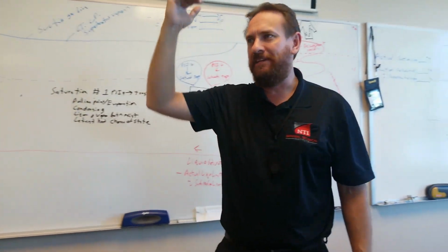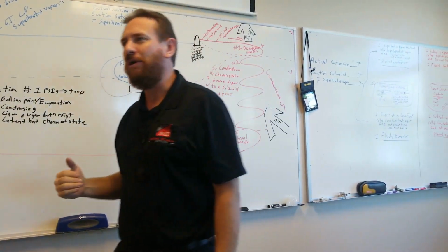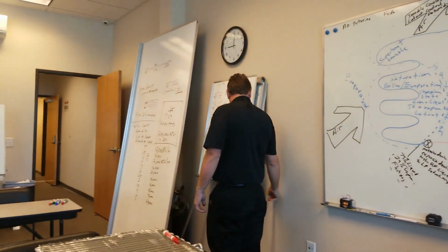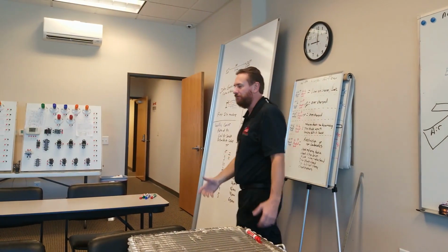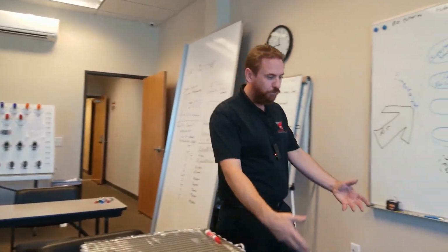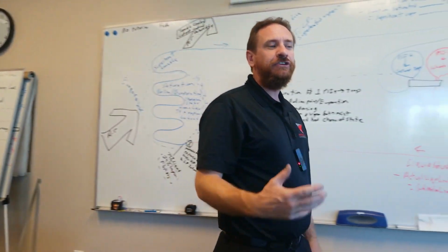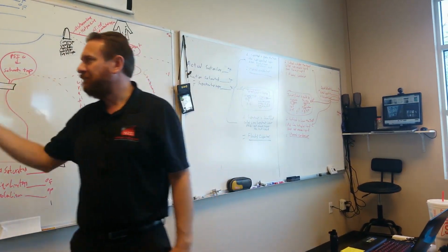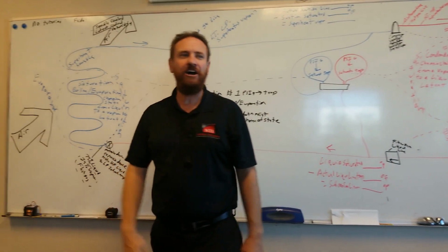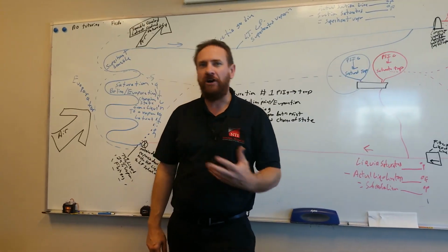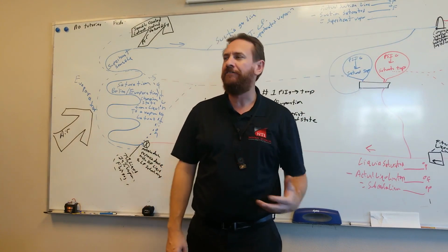And when I drop the temperature of that room very quickly, the air is the only thing that's really changing. But what else is in this room? Moisture, tables, people, walls, floors, everything. So the air very quickly heats back up, and the unit comes back on and very quickly cools it back off. And then it heats up very quickly, and it's on, off, on, off, on, off.